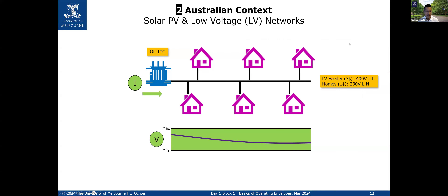What are these challenges? This is a schematic of a low voltage network — a few houses, a low voltage feeder, single-phase connected houses, and a transformer. When we design these low voltage feeders, we design them for a peak demand using an after-diversity maximum demand of a few kilowatts, ensuring conductor cross-sections and transformer ratings are sufficient, and that impedances don't create significant voltage drops. However, when we have solar photovoltaics, the sun shines on everyone, and if it's a weekday and not everyone is at home, we can have reverse power flows.